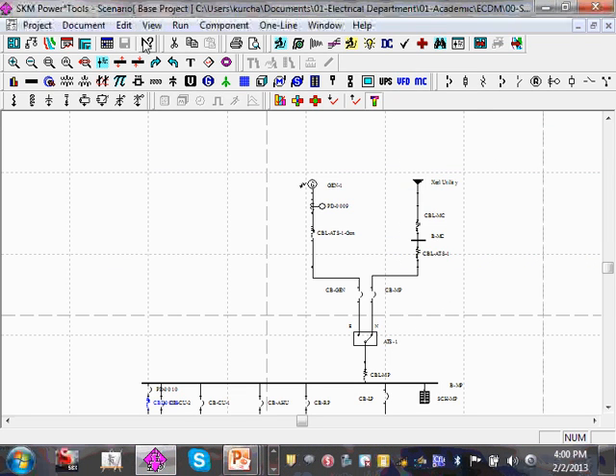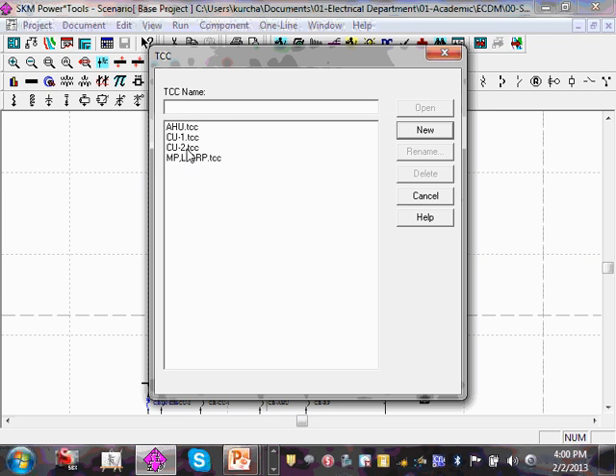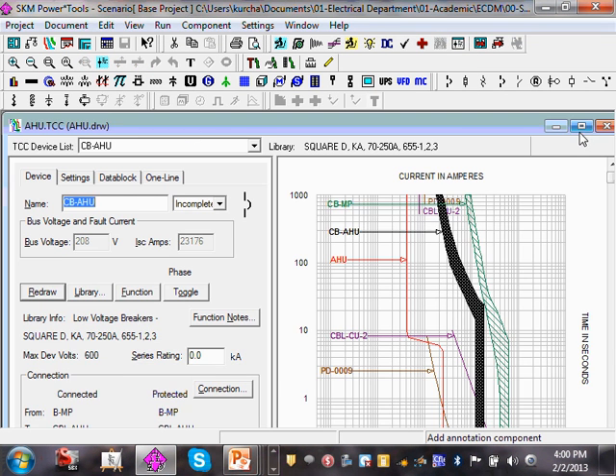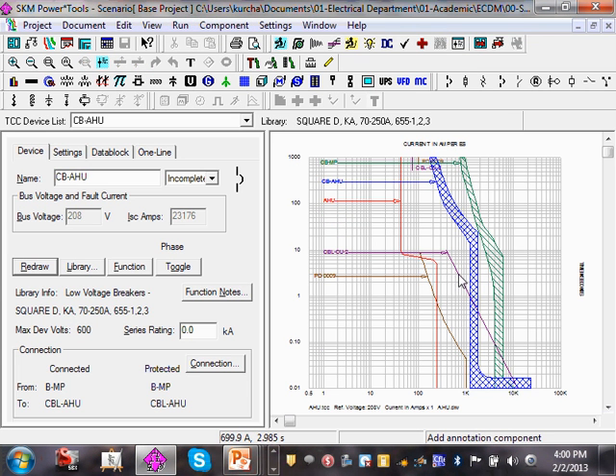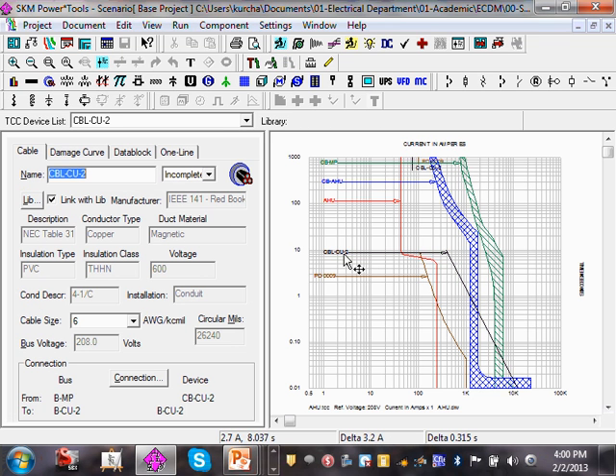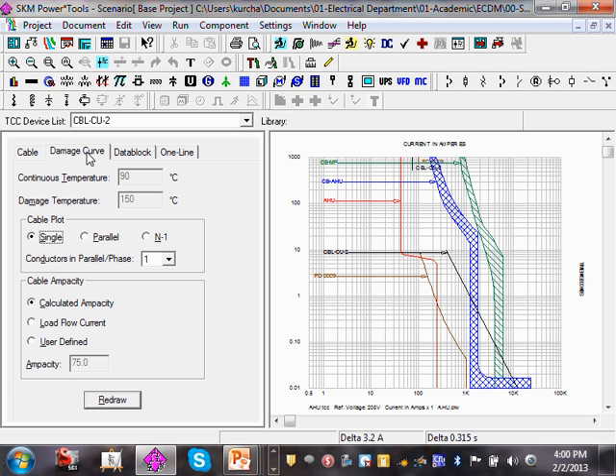And actually, I have one here. When we were looking at the system, I don't know if I just did not want to go there. Let me show you one of these damage curves for the air handling unit. If you look at the air handling unit, can you guys see that conductor here? Not that one here. Oops, there you go. That black thing, that's the damage curve for the conductor. So here's my damage curve for this conductor. Single phase. This conductor, that black thing, can carry 75 amps, 75 amps forever.